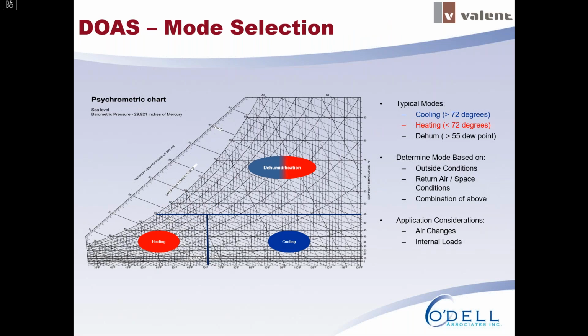So we talked about the different modes, but I'm showing them explicitly on this slide here. There's really three distinct modes of operation for a DOAS unit. You have heating mode, cooling mode, and dehumidification, and those are roughly the areas on the psych chart where you'll run into those modes of operation. Now, these modes are fluid, and actually a unit could be operating in those different modes all throughout the range of one day. Imagine fluctuations in temperature and humidity. It's not a very stagnant point. Those can change wildly.